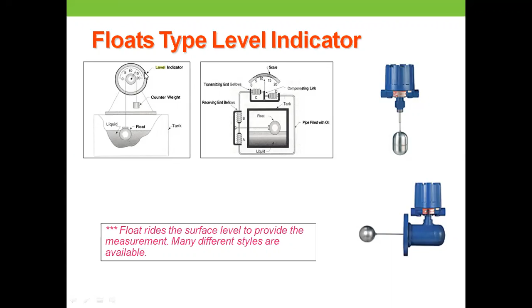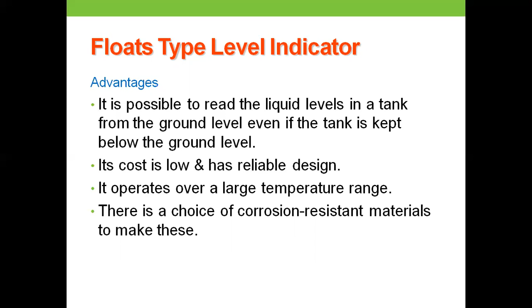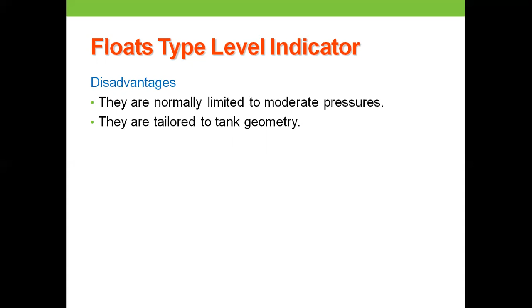And what are the advantages? It is very inexpensive, and it can be operated over large temperatures also, depending upon the type of material utilized for manufacturing the floats and even the indicator pointers used in the actual setup. Moving on to the disadvantages of float type level sensors: they are normally limited to moderate pressures. So high amounts of pressure cannot be handled by float type level sensors, and they are tailored to tank geometry, because irregular geometrical spaces existing over the tank will have a negative impact on the calculation. So these are the disadvantages of float type level sensors.